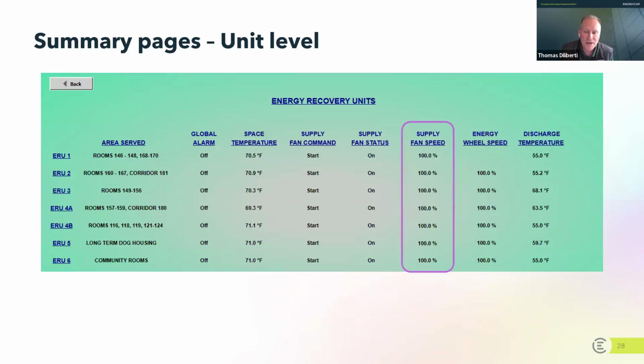This summary page, I wanted to bring to your attention here. If you notice these supply fan speeds, I'd mentioned how these VFDs, when they're at 100%, you're not taking advantage of the opportunity to save energy. So what I'm seeing here is every single one of these supply fans is running at 100%, and this is for an energy recovery unit. This is just very unusual.